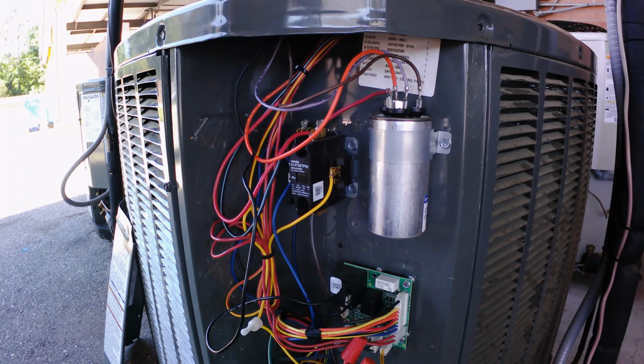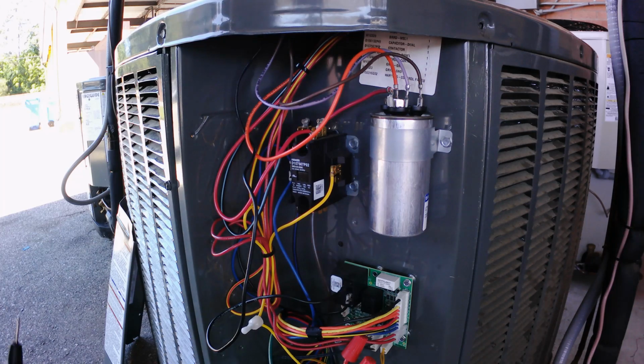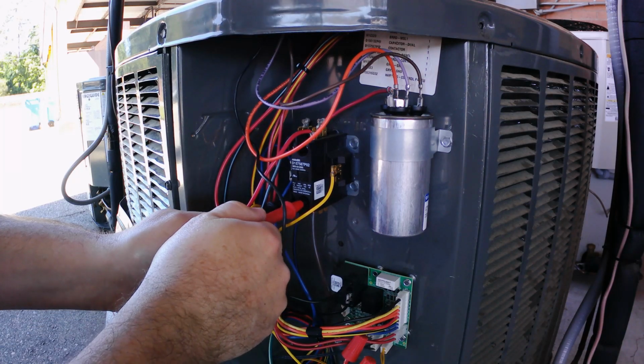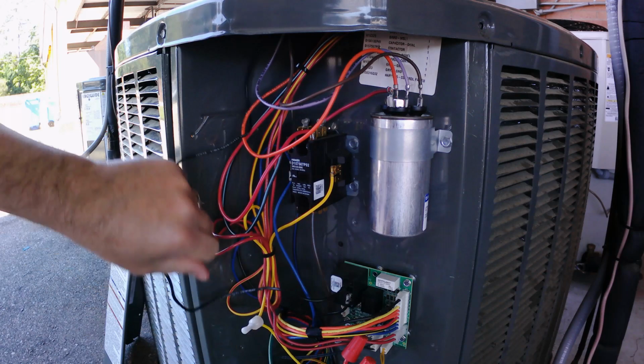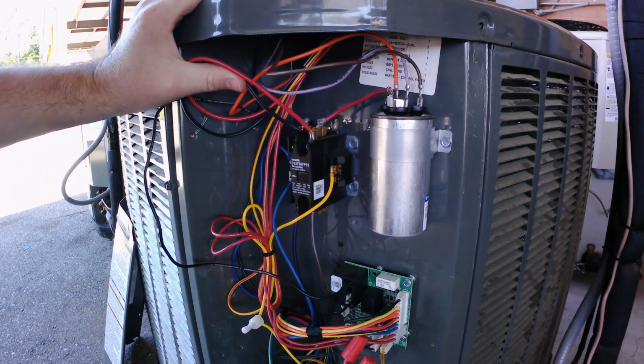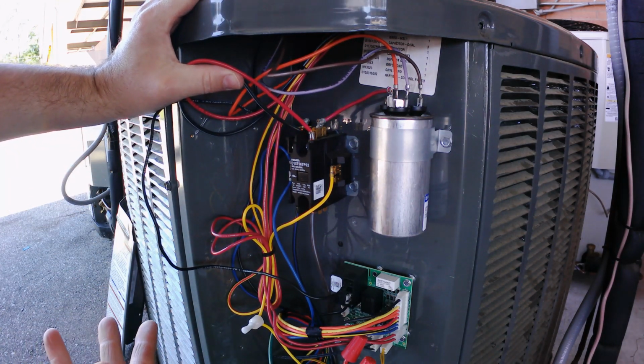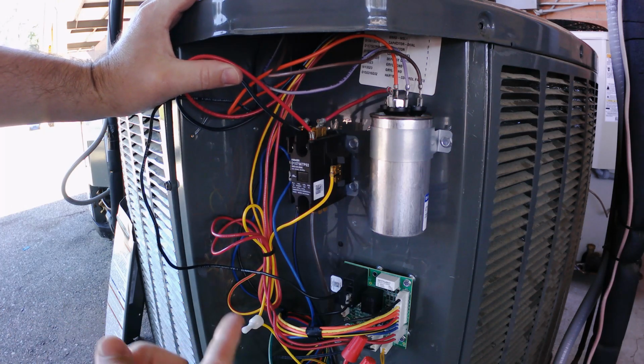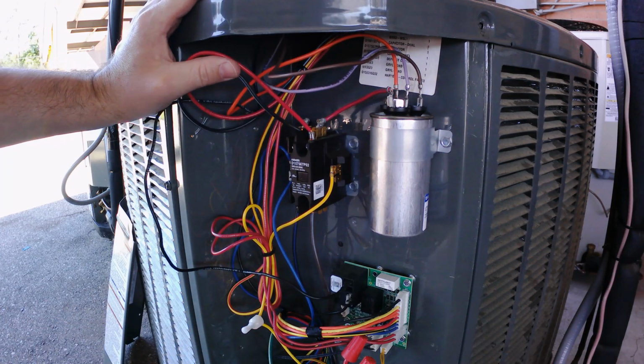Alright, so here we are on the outdoor unit for the air handler we just left, and what I'm going to do is keep the meter kind of off screen. I'm going to check the bottom here. I got no power. So if you're working with a PSC motor like a compressor that has the contactor and the capacitor and everything outside, I mean that's typical stuff.